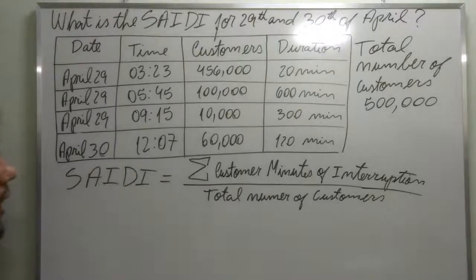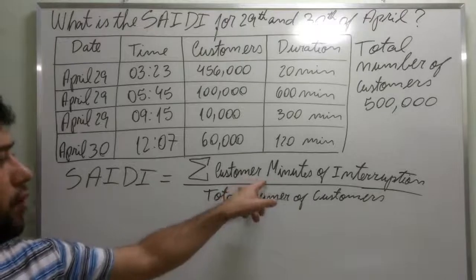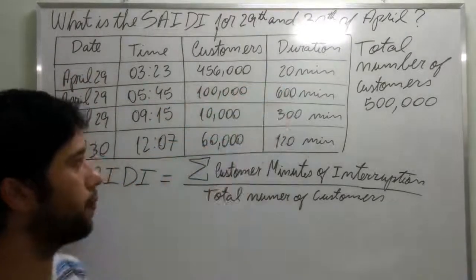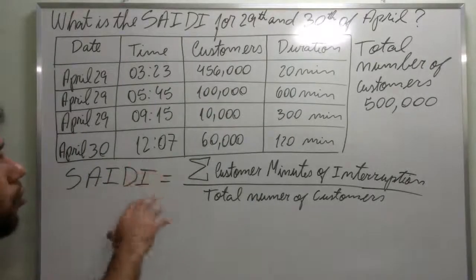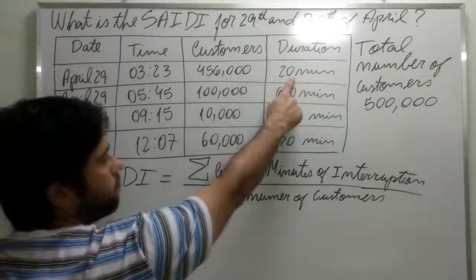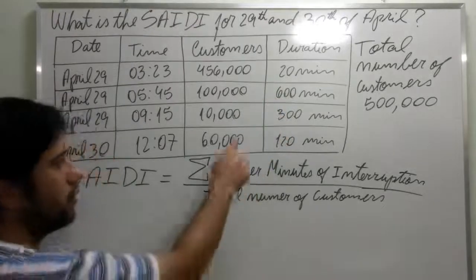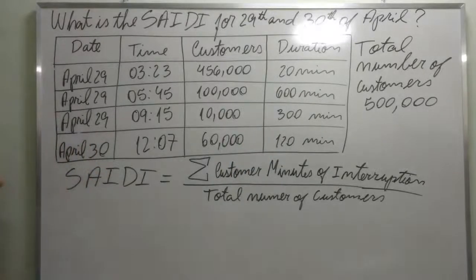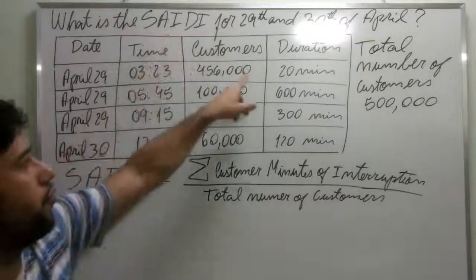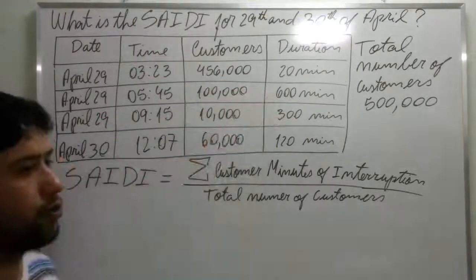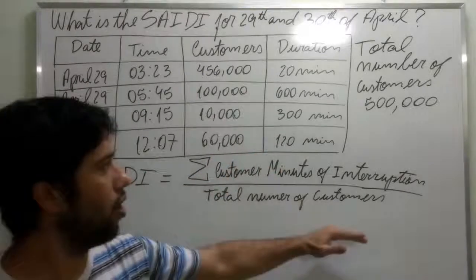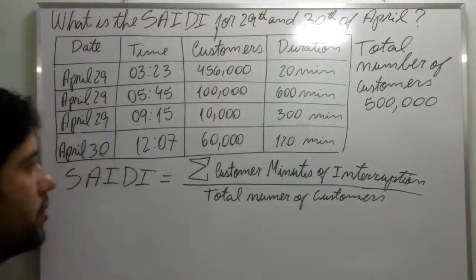The strategy to calculate the SAIDI for these events will be to multiply each number of interrupted customers by the corresponding duration of interruption for each event, sum all those products together, and divide by the total number of customers, which is 500,000.